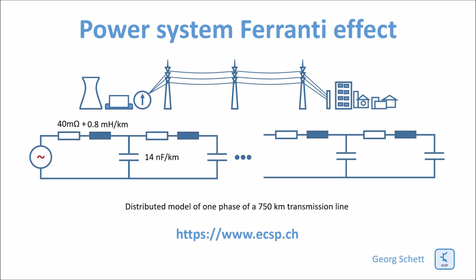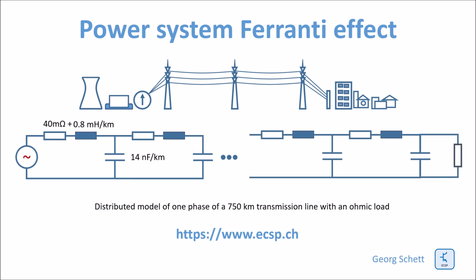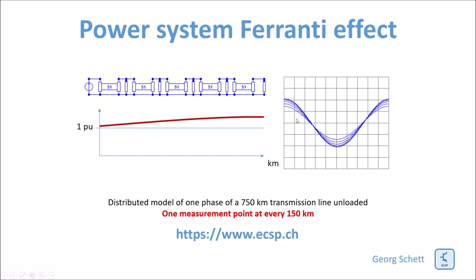Let's now come back to our distributed transmission line model and see what happens with an ohmic resistance at the end of the line. Here I have a 750 km line subdivided into five segments, measuring the voltage between each segment. You can see the traces of the individual voltages on the graph. The lowest voltage is the source voltage, and each segment shows increasing voltage until the highest voltage at the load end. In this case I have a very low load, meaning a high resistance, so the Ferranti effect is fully materialized.